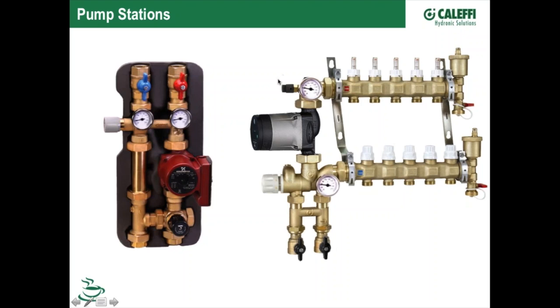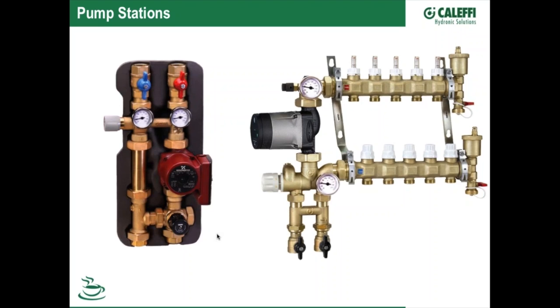If you want to build your own version of this, we sell the individual component here. Notice that we offer this with the high efficiency ECM type of pump, which is perfect for this application. If we're going to start adding zone actuators on this, this pump now has the ability to regulate its output based on what these valve actuators are doing as they open and close. We're going to change the speed of that, or the fixed speed pump we're showing here, thermostatic valve here, supply and return, blue and red to note the supply and return, and temperature gauges so you can see what kind of a delta T you have going through that system there.